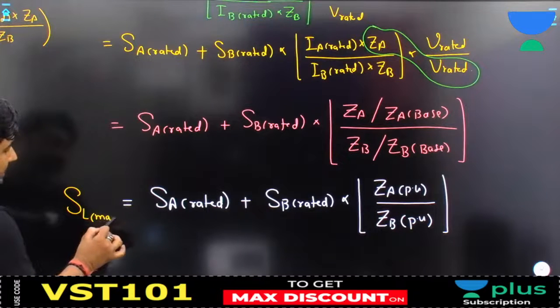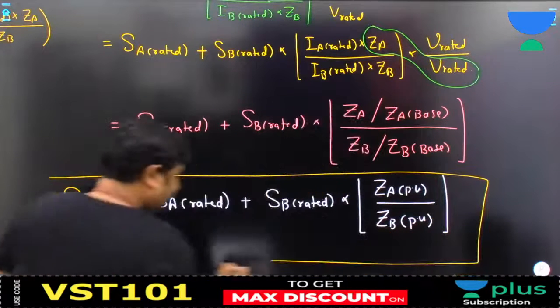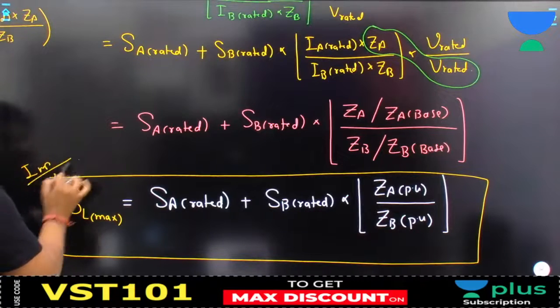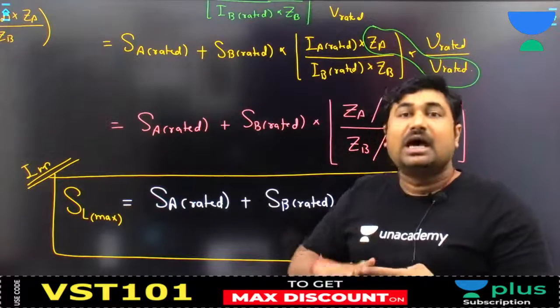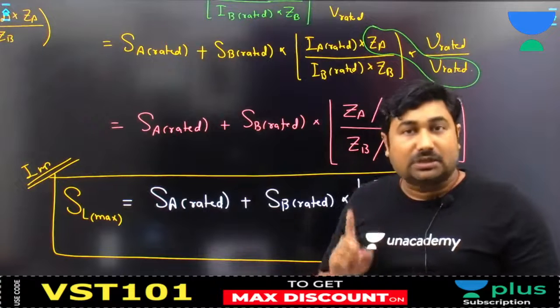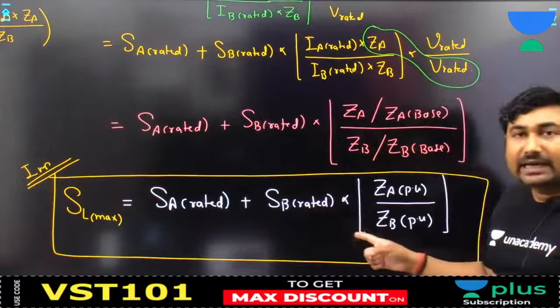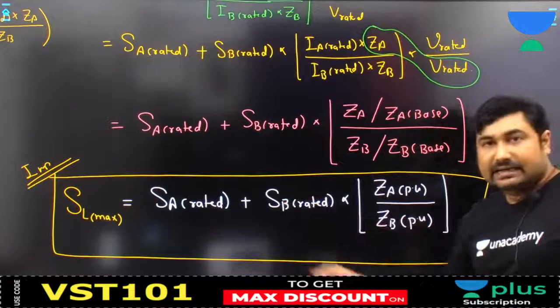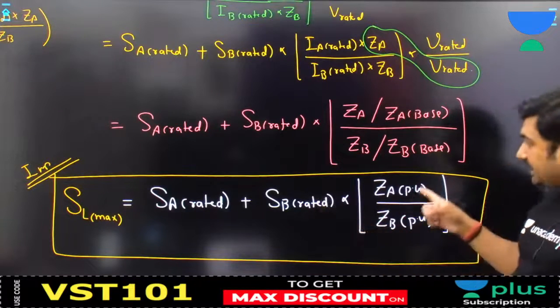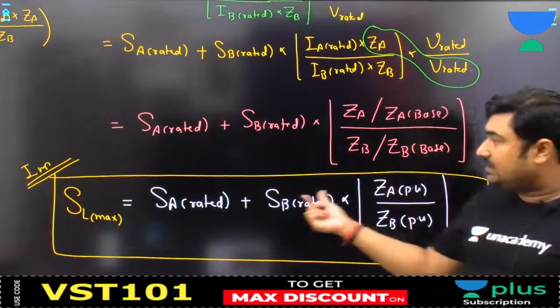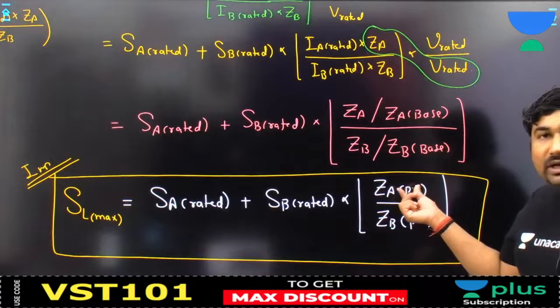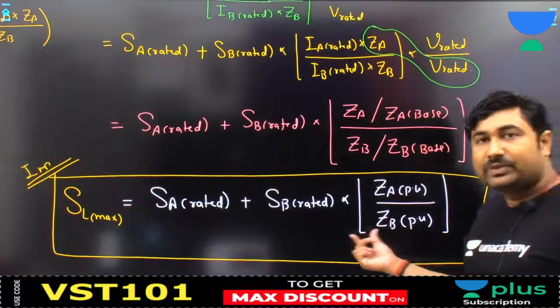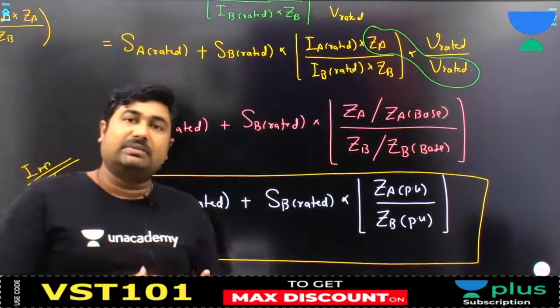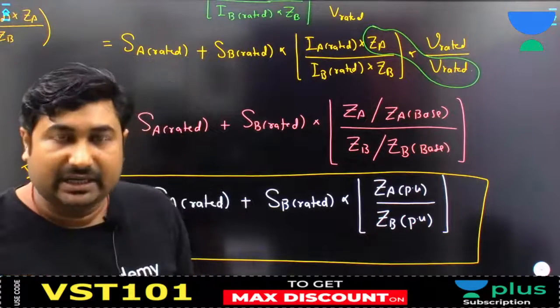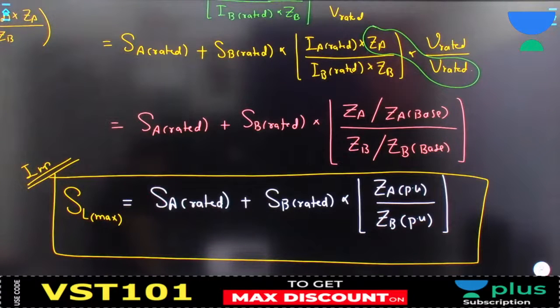You need to share the session as much as possible. So please, now you know about this formula. Sir, we have to take the rated kVA of that transformer whose either actual ohms or per unit impedance is lower. And then the other transformer will operate at a value less than rated, and that can be calculated approximately as SB rated into ZA upon ZB. So the impedance which is lower goes upward and the higher one is in the denominator. Is it okay? You can use this formula to find the maximum kVA that the parallel combination can feed during parallel operation. Are you able to understand?